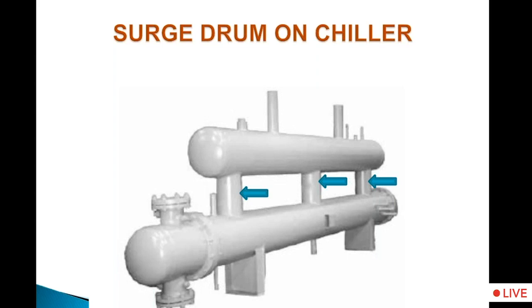And therefore, instead of increasing the surge drum size, if you just add more number of pipes between the surge drum and the vessel, then your velocity will fall down and the liquid ammonia will fall down into the chiller by gravity. No gas liquid will enter into the compressor suction. So it is very important to use more number of pipes than a single pipe. People use a single pipe and then the velocity is very high. Try to maintain the velocity of ammonia around 75 feet per minute, not higher than that.